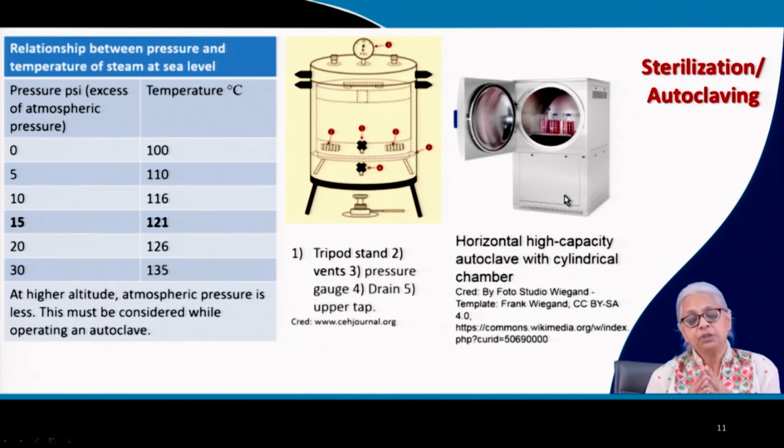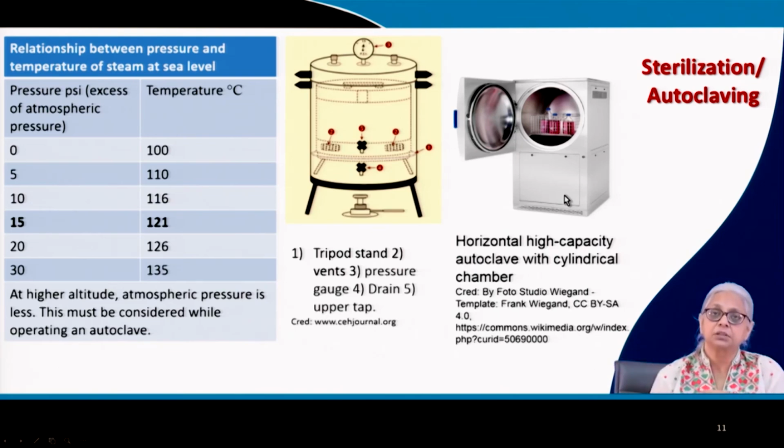Now, a very important point in autoclaving is that the entire cycle, in practical terms, from the point of closing the door to the point when it is safe to reopen the door, can be anywhere from 1.5 hours to 3 hours or so. But the actual autoclaving time is actually 15 minutes because it takes a fair amount of time for the steam to build up.